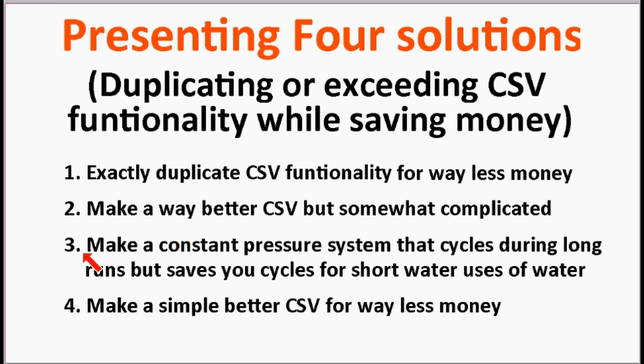The third solution is kind of not really a cycle stop valve, but it's a way that you can get constant pressure that cycles during long runs but saves you cycles for short runs. So a cycle stop valve is good for long runs. It won't cycle during long runs, but the problem is it cycles every time you turn on the water.